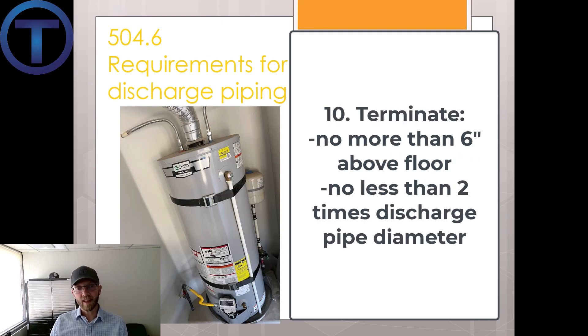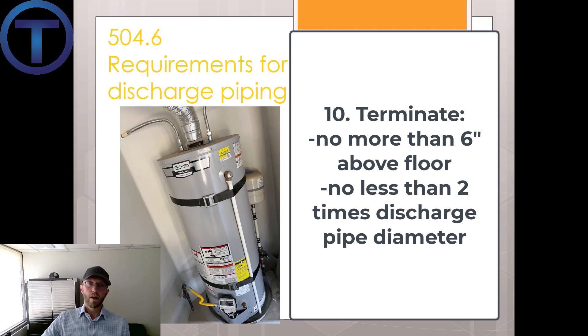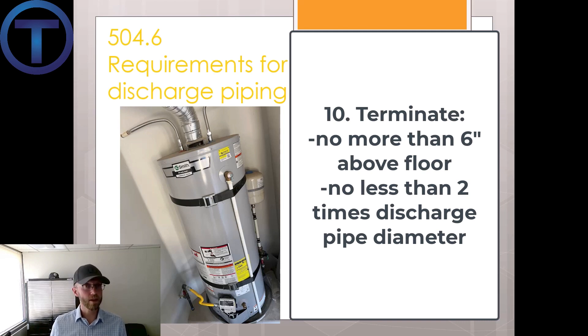Number ten: terminate not more than six inches above the floor and not less than two times the discharge pipe diameter above the floor. Two times the pipe diameter is the air gap. We don't want the pipe cut short and just coming halfway down the water heater spraying water — we could get burned as we approach. So at a maximum six inches above the floor, but at least two times the pipe diameter, which is typically about one and a half to two inches.